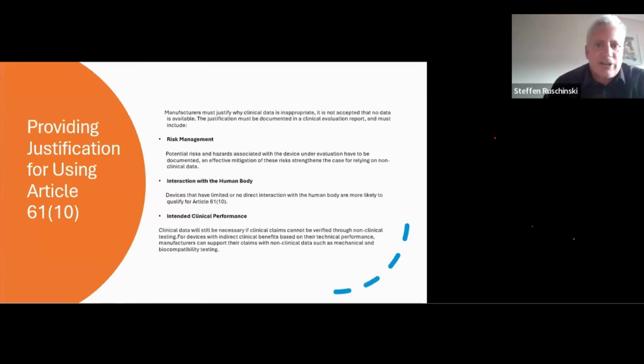Manufacturers still must justify why clinical data is inappropriate, and just like I said, it is not accepted that no data is available. Justification must be documented in the clinical evaluation report. It must include the risk management with potential risks and hazards associated with the device under evaluation, effective mitigation of these risks, and the interaction with the human body. Devices that have limited or no direct interaction with the human body are more likely to qualify for 61(10). Intended clinical performance and clinical data will still be necessary if clinical claims cannot be verified through non-clinical testing.